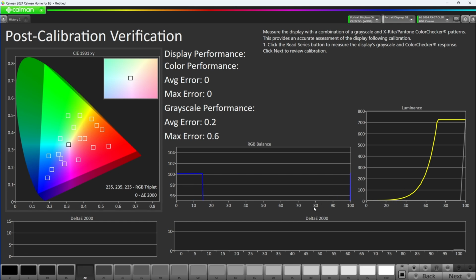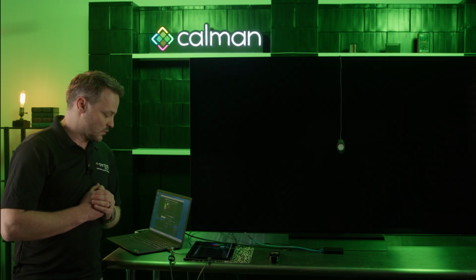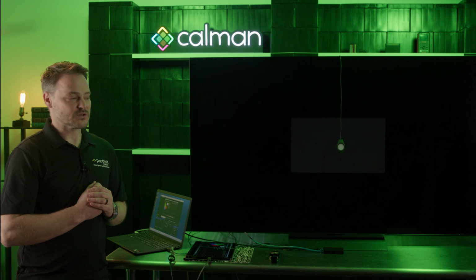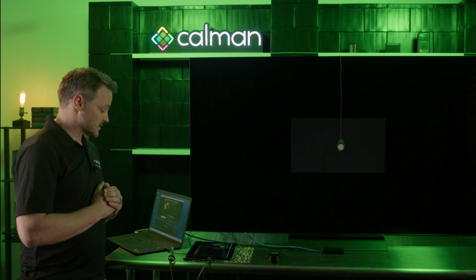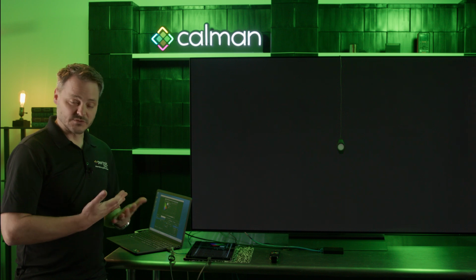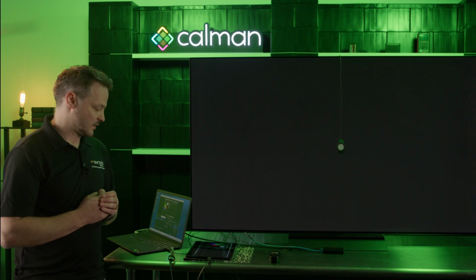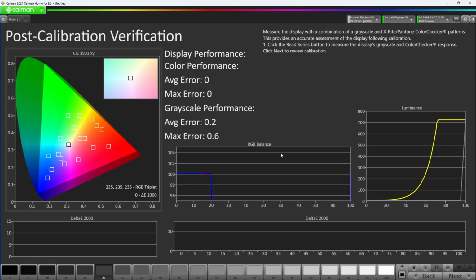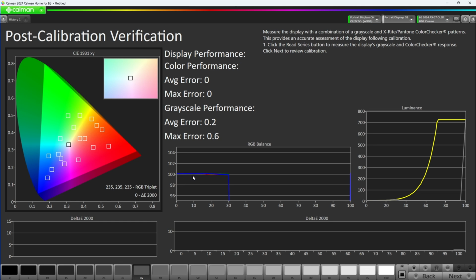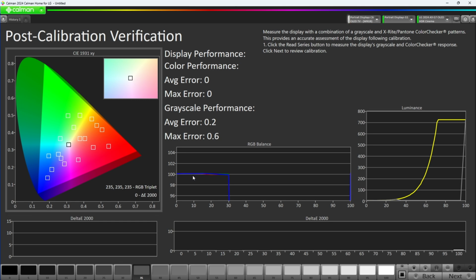The DE chart gives us our measurement of how close or far off we are from our targets. In this case, what we would hope to see is that our DE values are as close to 0 as possible, ideally under 1. The red, green, and blue RGB balance chart tells us how accurate our white point is for our D65 target. What we anticipate seeing after calibration there is that the red, green, and blue bars all match up together and are all centered right along the 100 line.